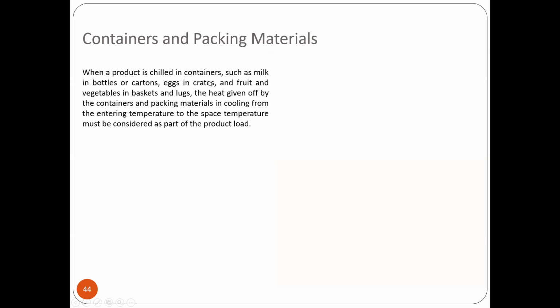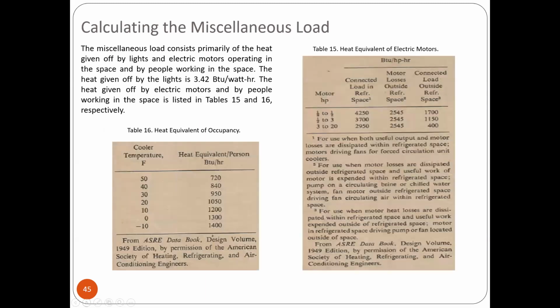May example na tayo. Containers and packing material. When a product is chilled in containers such as milk in bottle or cartons, eggs in crates and fruit and vegetable in basket and lugs, the heat given off by the containers and packing material in cooling from the entering temperature to this space must be considered as part of the product load. Siyempre. So, calculating miscellaneous load.